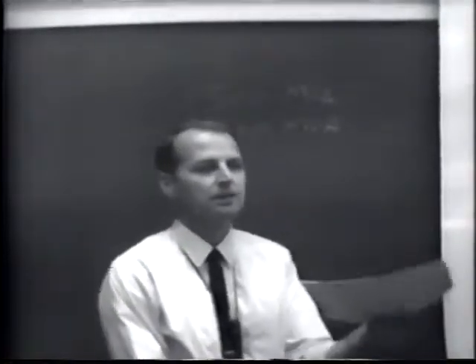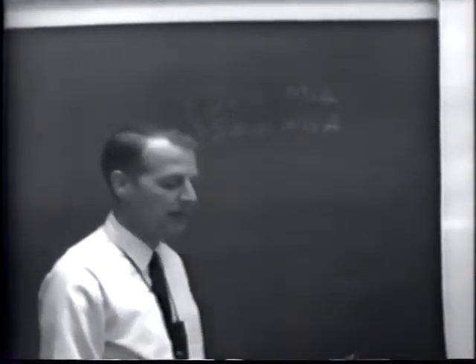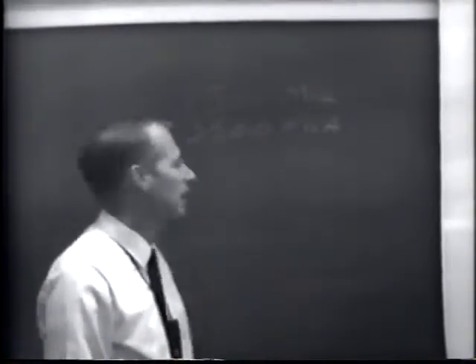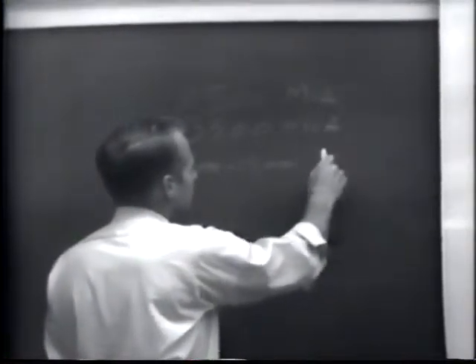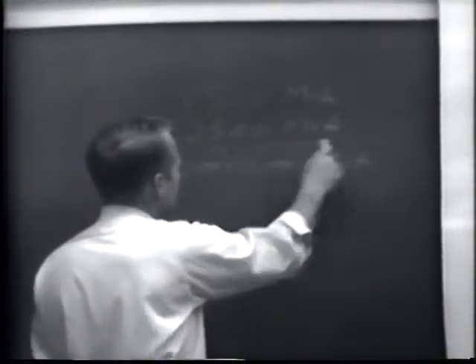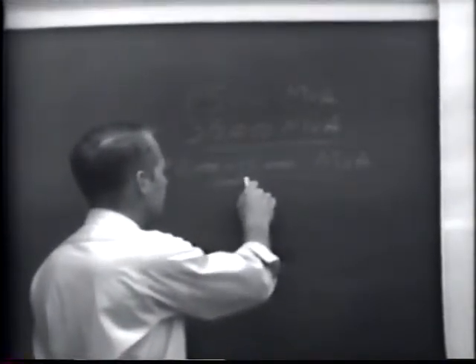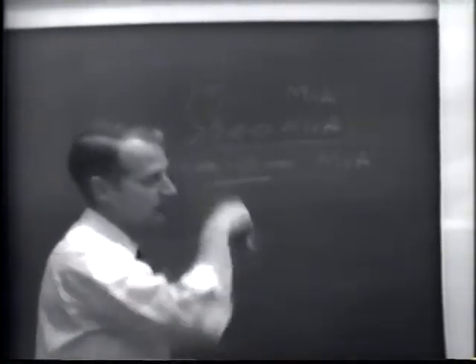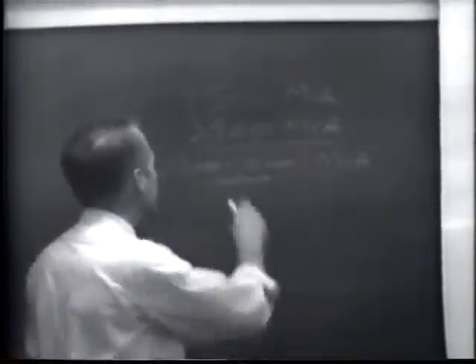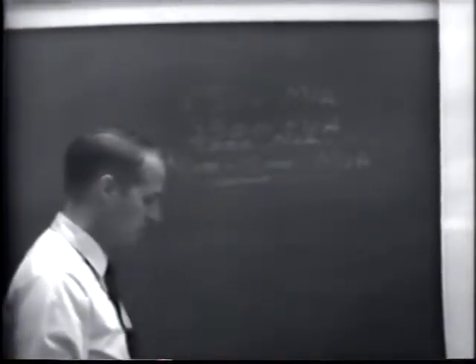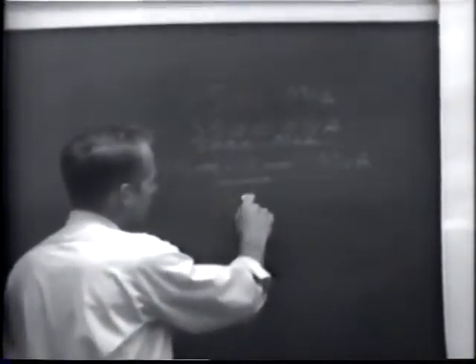The 161 kV, we go up quite rapidly in interrupting capacity. The ones we're buying now range from 10,000 to 15,000 MVA, with continuous ratings of 1600 to 2000 amps. At 69 kV, let me backtrack a minute. At 2 or 3 of our locations now, we're buying 5,000 MVA circuit breakers. And the 345 kV breakers are 25,000 MVA.